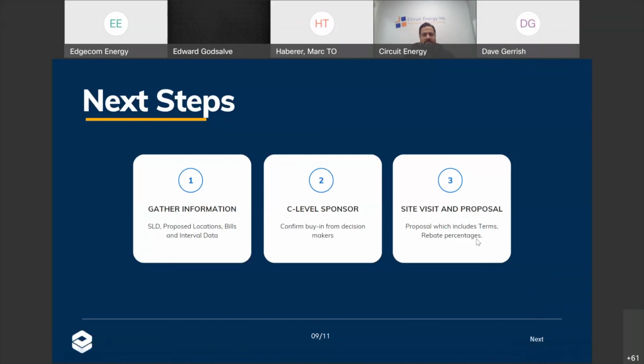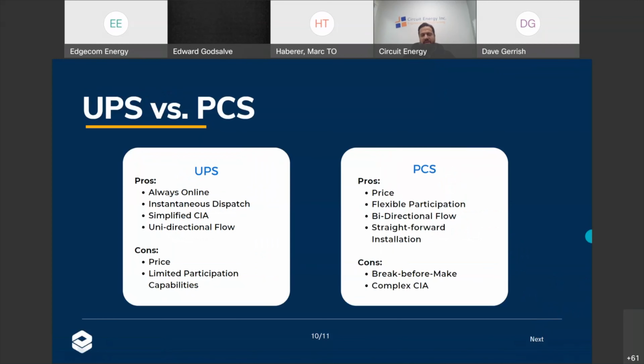On to the next slide, I'll talk about some of the questions that typically come up. There are two different types of systems we typically propose: UPS versus PCS. It's worth mentioning that about 95% of our proposals and projects in the past have been PCS, but they both have their pros and cons. On the UPS side, if you've got a very sensitive facility that has to always be online and can't even have 100 milliseconds of voltage drop, then we'll look at a UPS system.